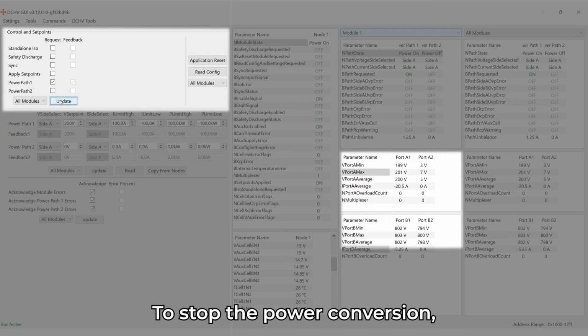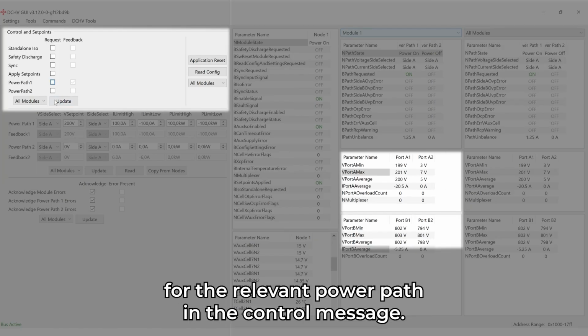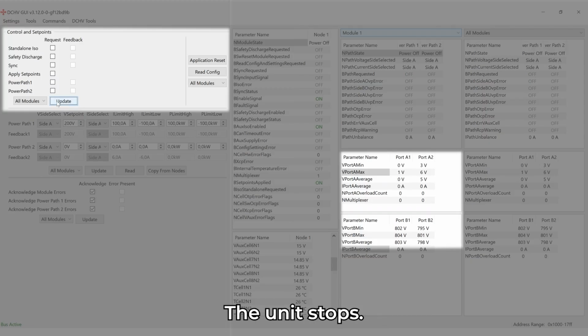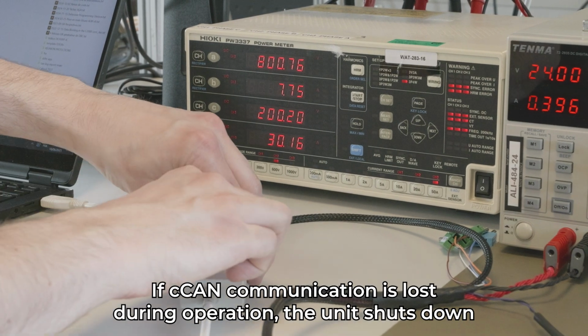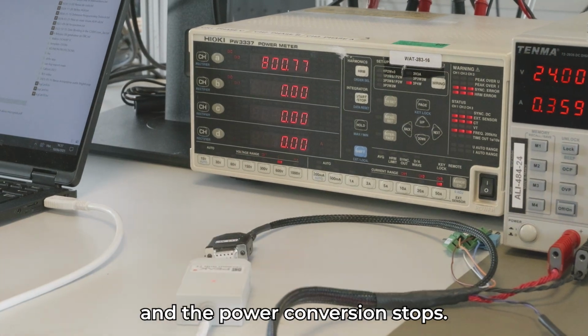To stop the power conversion, clear the power on request for the relevant power path in the control message. The unit stops. If CAN communication is lost during operation, the unit shuts down and the power conversion stops.